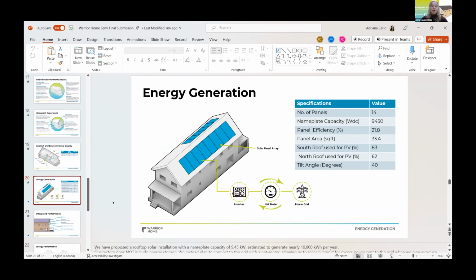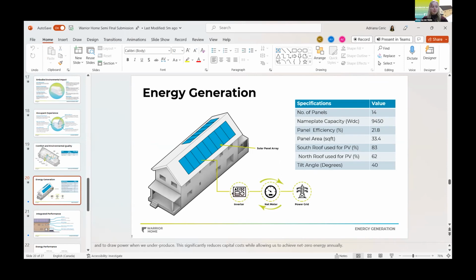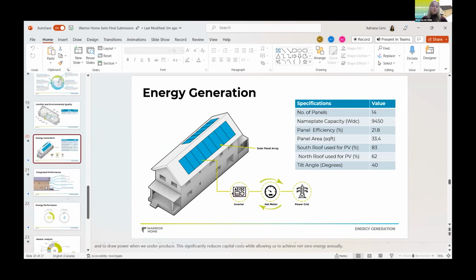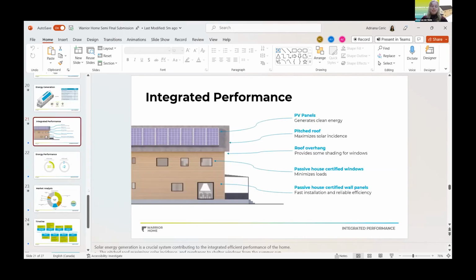We estimate it will generate nearly 10,000 kilowatt hours per year, accounting for significant losses from snow. Our system does not include any energy storage. Instead, we plan to connect to the grid using a net meter, allowing us to draw power when we underproduce and receive credit for power provided to the grid when we overproduce. This significantly reduces capital cost while still allowing us to achieve net zero energy annually. We've selected a string inverter so the system is islanding capable in the future.